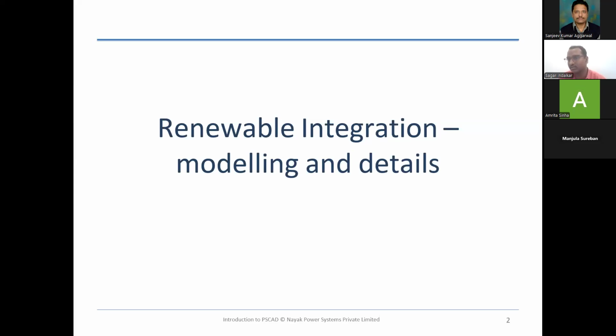And how can we know what behavior is to be expected from a particular renewable energy plant? It is not known unless we perform certain studies, right? These studies are performed in the RMS domain as well as the EMT domain. And the tool which is preferred to perform these studies is called PSCAD. It's an EMT simulator. You can model controls in it. You can model switching-based power electronics in it. It can capture harmonics, all levels of detail of a renewable energy plant. And that's the reason there is a need to perform renewable integration studies in PSCAD to confirm that the plant you are installing complies with the Indian grid code, or whatever country it is being installed in.